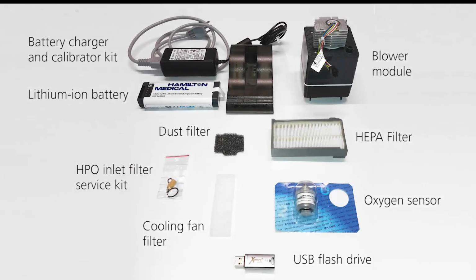The following parts are required for preventive maintenance: a battery charger and calibrator kit, a Hamilton T1 lithium-ion battery, a blower module, an HPO filter service kit, a fan filter, a dust filter for the HEPA filter, a HEPA filter, a galvanic oxygen cell, and a USB flash drive.